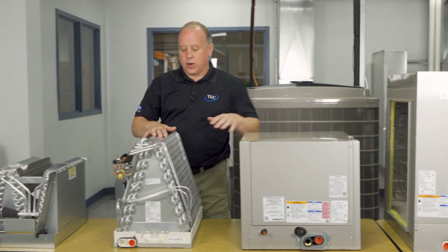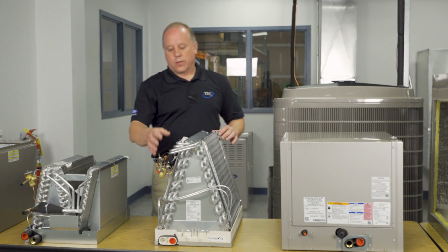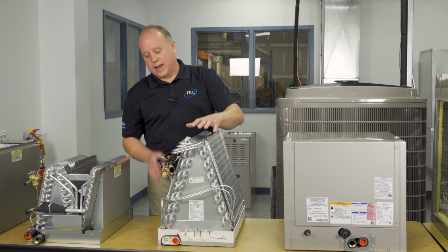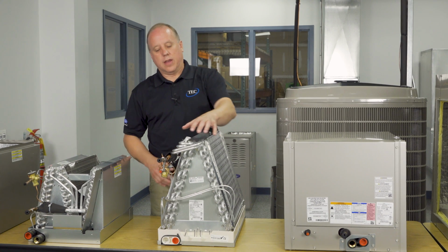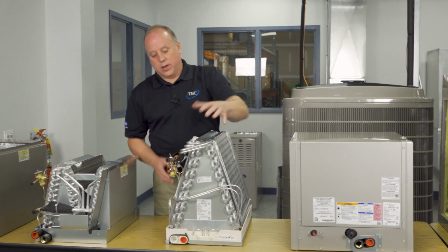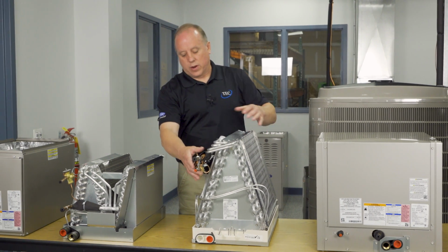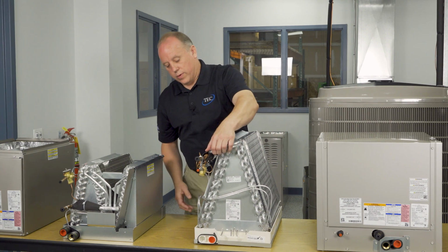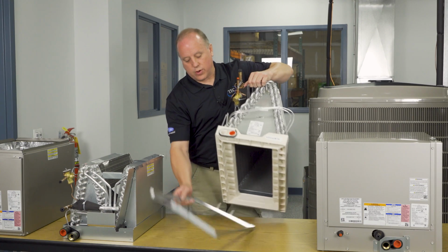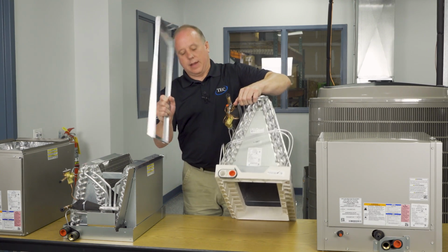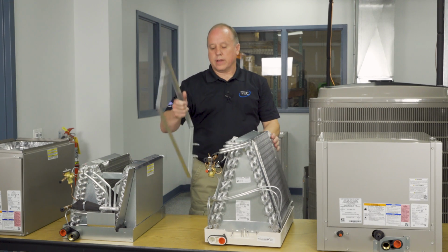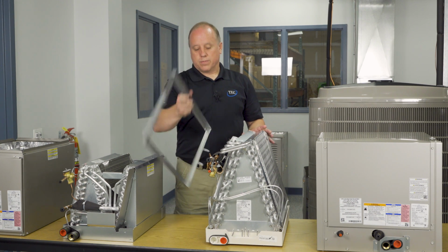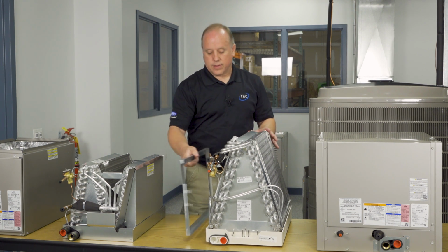Our uncased A coil, pretty straightforward, goes back a long time. Probably used to be the most common coil used. Now, end coils are pretty common these days, but you have the uncased A, put into the ductwork, slid in, we come around it. When we do get these coils, they come in the box, we uncrate them. When you do pull it out, the coils do come with a coil pan that's attached to the bottom. Sometimes, because it's taped on there and sealed pretty tight, it does look like it's part of that coil pan. We do want to remove that from there. So that comes along with the A coil.